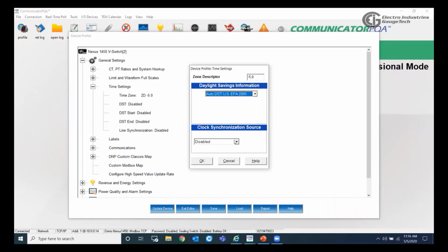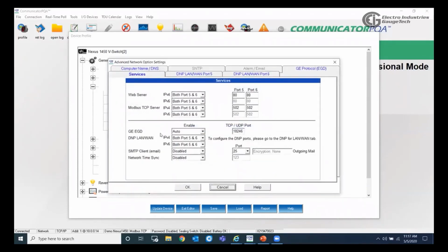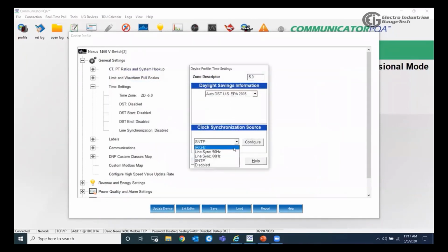We also have the synchronization option. If the meter is connected to a network and we have the network time protocol, we can choose that. If we choose that, we have to configure it by choosing which port is used to connect to that network. We will talk about this in more detail when we talk about the communication ports. If we don't have that option, we can choose the line sync 60 Hertz and hit OK.